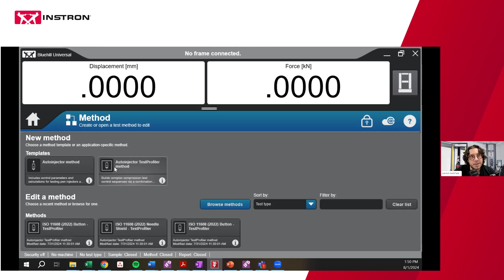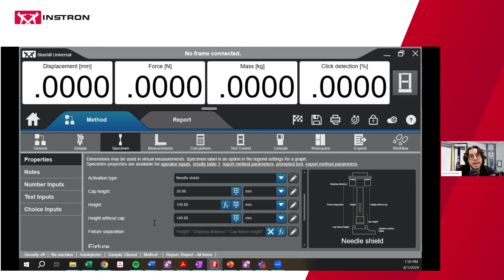They show a typical device and use terminology that you would typically use within the industry. You have the ability to change whether it's a two-step needle shield or button activated device, which will dynamically change what dimensions it asks for. And that will also change how it tries to control the test. So if I go to test control, anyone who's used the older version, or if they're familiar with Test Profiler, that's typically how the auto injector is run. It's a series of blocks to control the crosshead, all of the grips, how we interact with the device, and how we interact with some of the additional transducers.